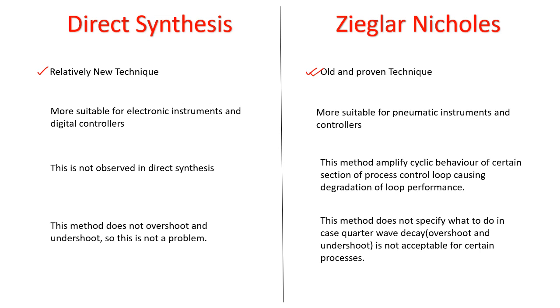The Ziegler-Nichols technique produces a loop that tends to ring like a bell. If the bell is hit at the right time, the bell can get much louder. In process control, this means the loop will amplify, not attenuate, in certain bands of the cyclic process behavior. In other words, the technique can degrade the process under certain conditions.